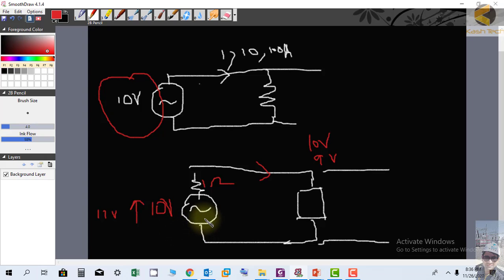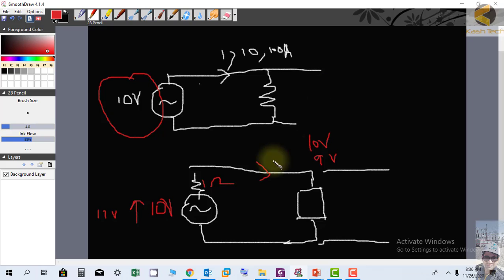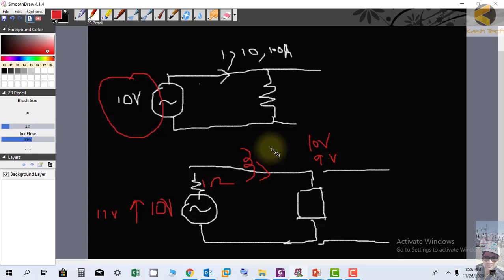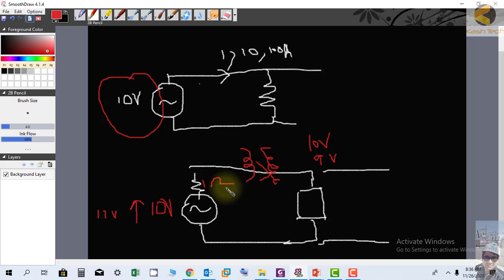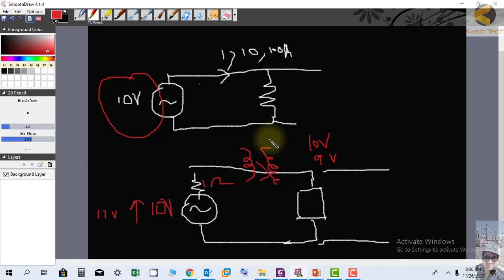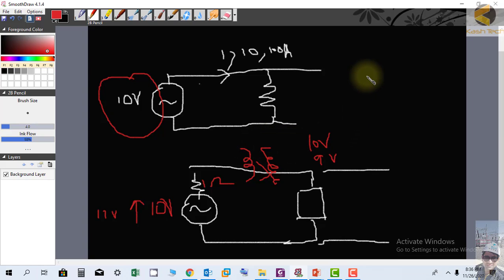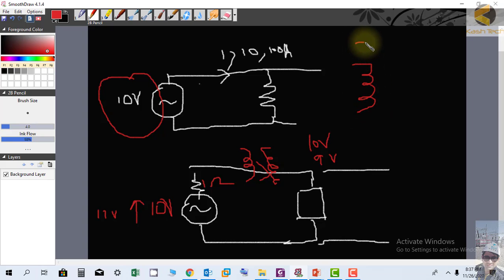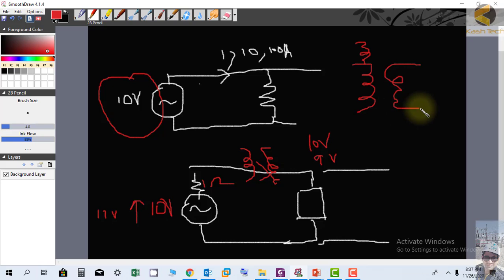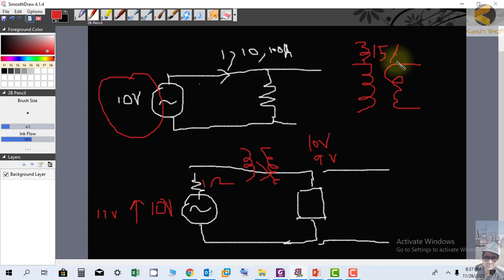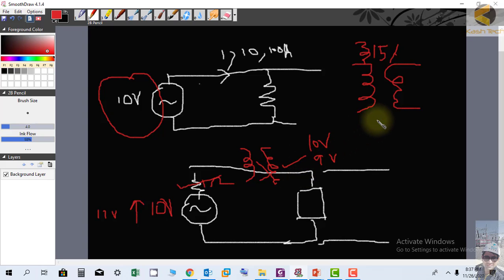This is one form. Another form is normally the load is supplied through the generator and through some transformation network. So transformer is installed between generator and the load. One option could be to change the voltage, increase the voltage to maintain the supply voltage by tap changers. So each transformer is also provided, you can see this is the transformer, and tap changer winding is provided which can provide voltage regulation, for example, up to 15 percent. So whatever is the voltage drop in the source impedance or voltage drop in the line is compensated by the tap changer winding in the transformers.